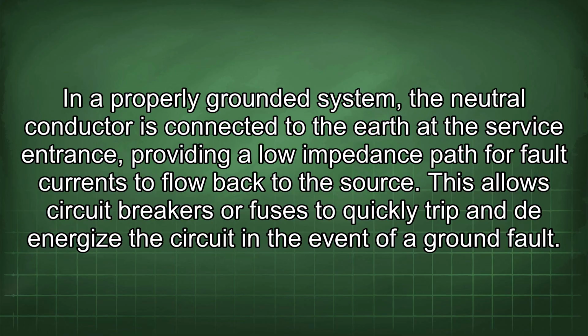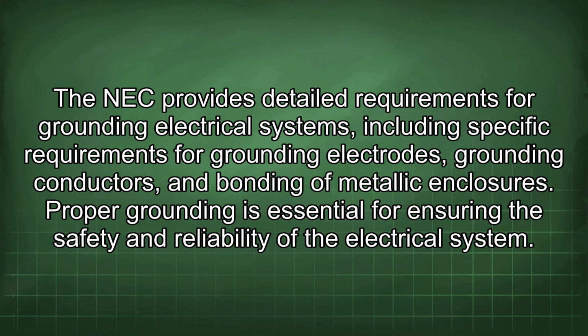This allows circuit breakers or fuses to quickly trip and de-energize the circuit in the event of a ground fault. The NEC provides detailed requirements for grounding electrical systems, including specific requirements for grounding electrodes, grounding conductors, and bonding of metallic enclosures. Proper grounding is essential for ensuring the safety and reliability of the electrical system.